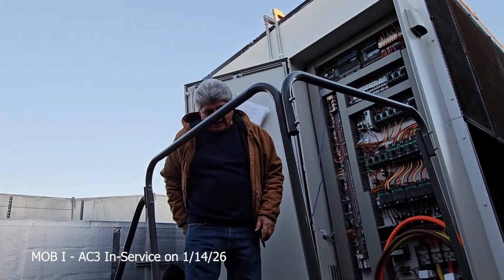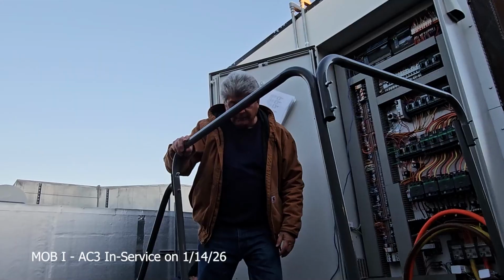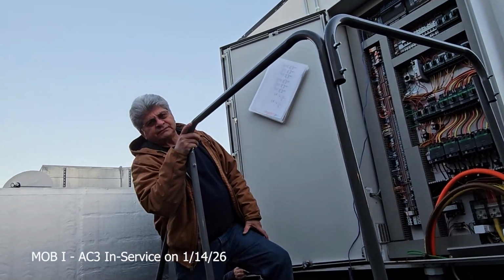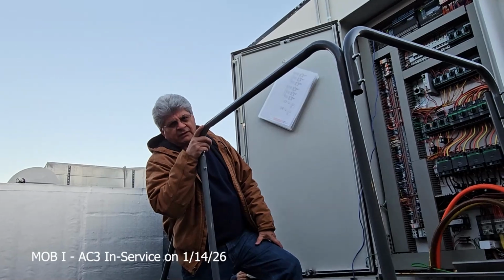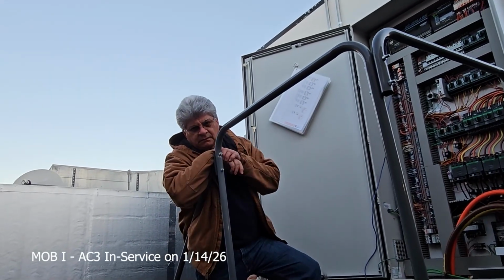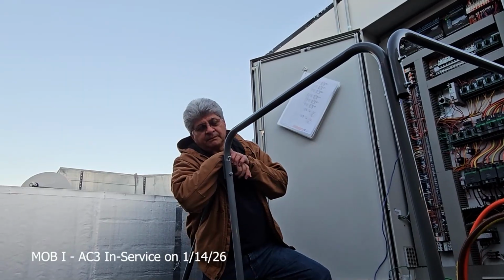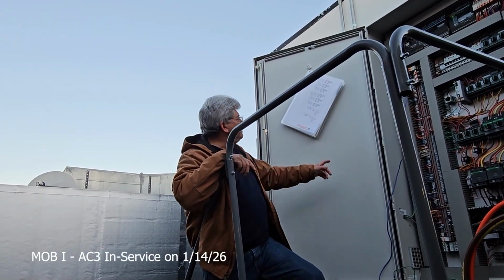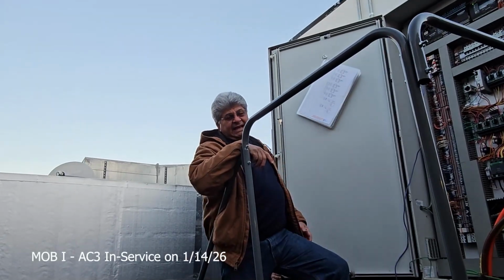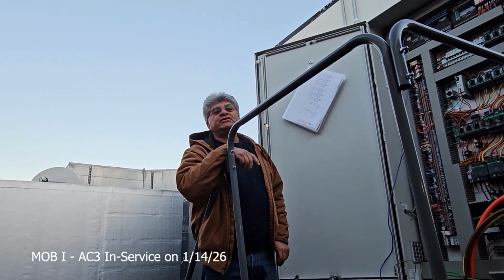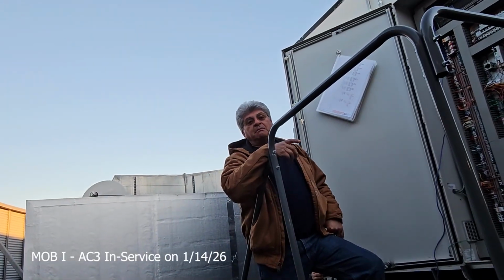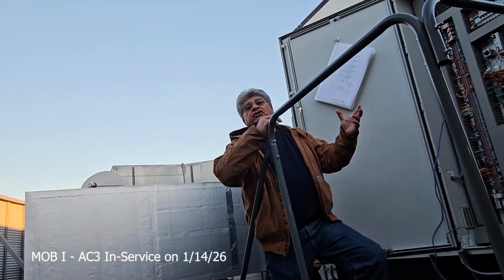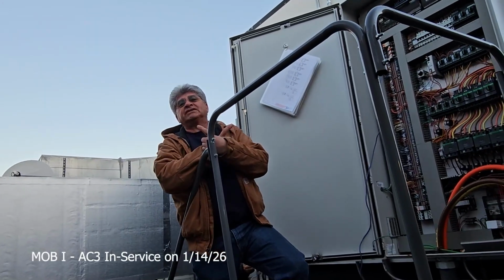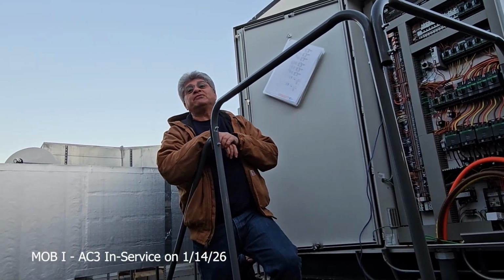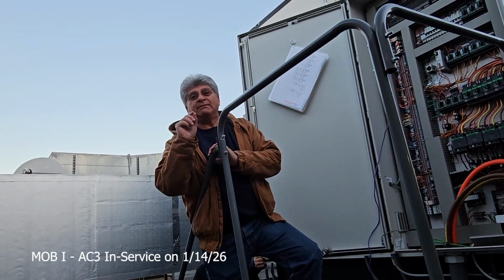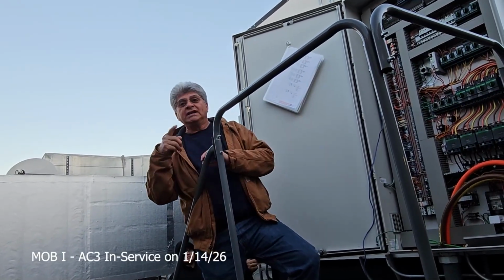On the ECM motor, I'm not familiar with that motor, but the stupid question is, does it have the wiring? Does it require... All your wiring for your ECM motors will be on here. Yeah, but it's not like rotation. It's not going to change rotation if you change it. You can never change rotation on an ECM motor by switching wires around. You guys all know to change a rotation on a 3-phase motor, just change 2 legs. Right. You change 2 legs on an ECM motor, it's still going to run the same way. It's going to run the same way it was programmed. All these were programmed at the factory to run in one direction.